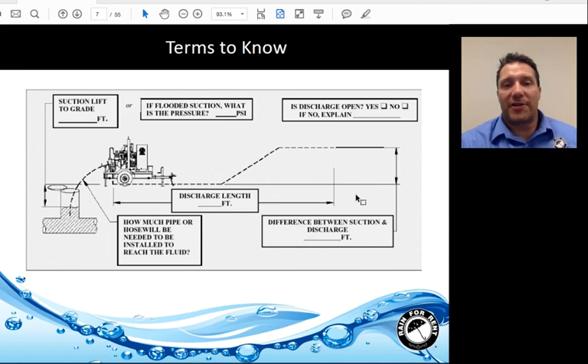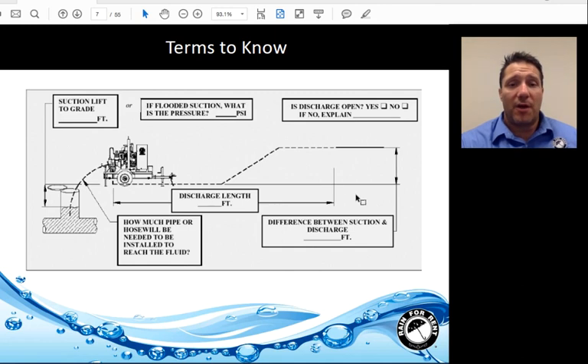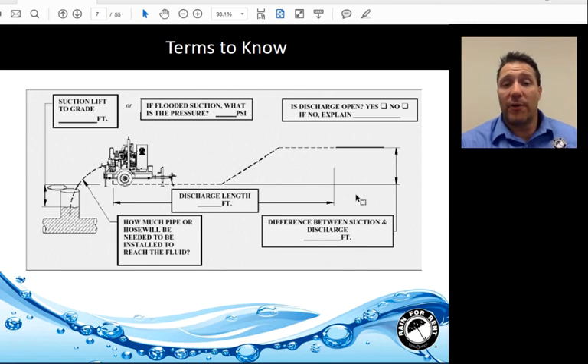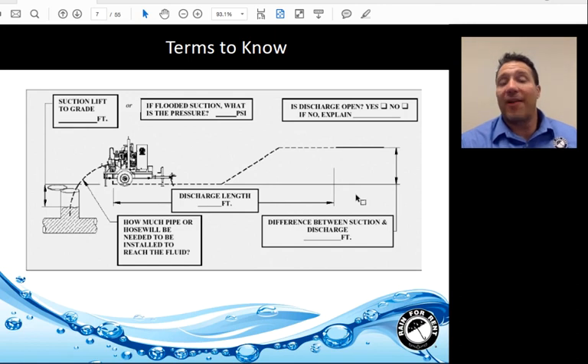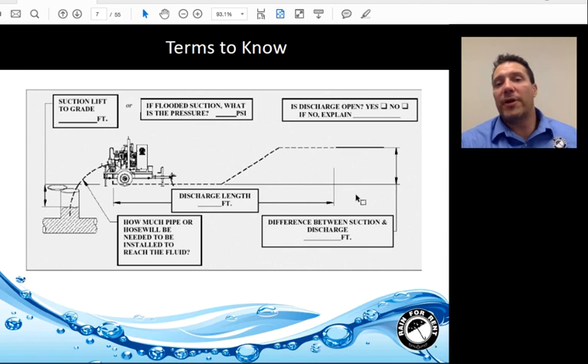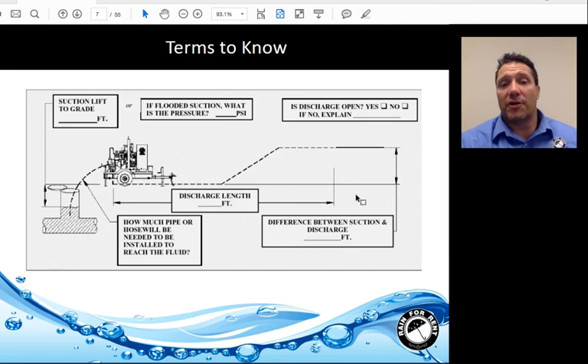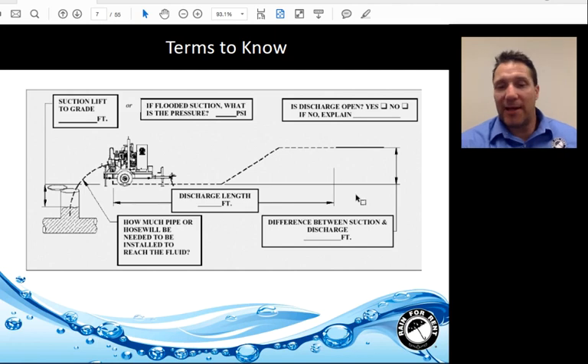This is a graphic representation of the items we just discussed. In the upper left-hand corner you can see suction lift to grade, how much pipe or hose will be needed to reach the fluid, the discharge length, and the elevation change over the discharge length. An open discharge means you are open to atmosphere — no required pressure at the end. A closed or non-open discharge, such as a force main, means the system must perform at a particular pressure at the end of the temporary system.